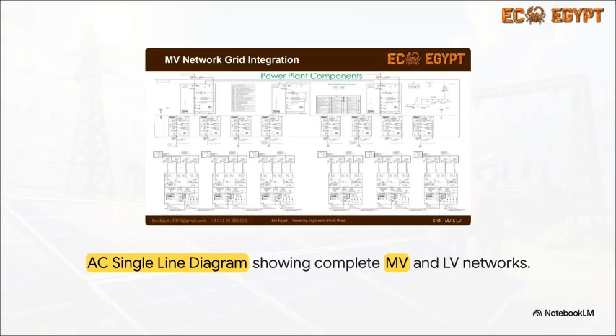If you trace the AC single-line diagram here, you can visually follow the whole flow of the ecosystem. It's pretty cool, actually. Power starts way down at the bottom from the solar modules, moves into the string inverters, and then gathers at the LV main distribution boards. From there, it flows up into those step-up transformers we just mentioned, and finally pushes out into the MV switchgear network through the RMUs, heading straight for the utility grid interconnection. It's just a beautifully structured hierarchy of power when you really look at it.